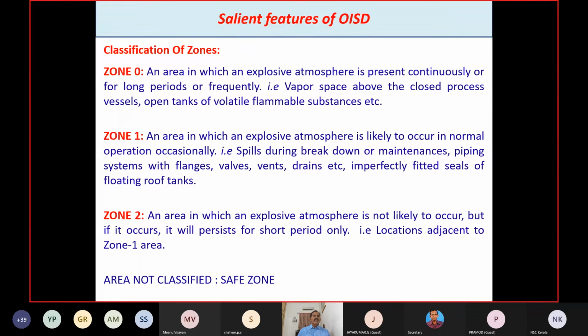Zone 1 is an area in which an explosive atmosphere is likely to occur occasionally in normal operations. For example, while doing any maintenance job, some spills will occur during breakdown or maintenance, while opening the flange of any pipeline, and some fugitive emissions from vents or drains, etc. Also imperfectly fitted seals of floating roof tanks. So this will happen occasionally in normal operations.